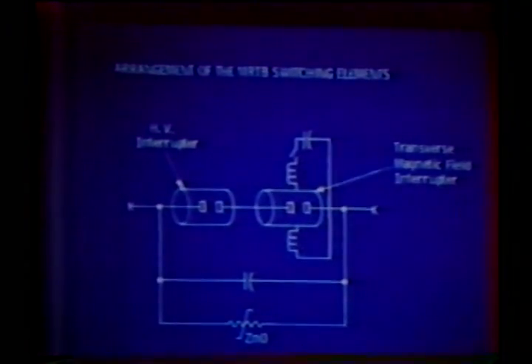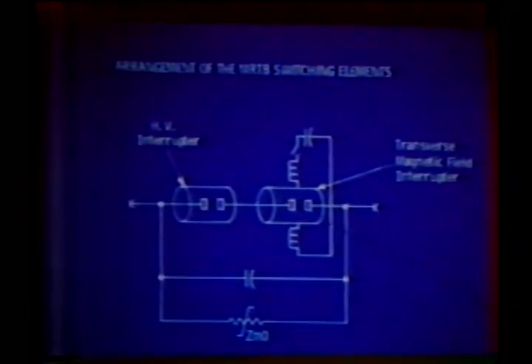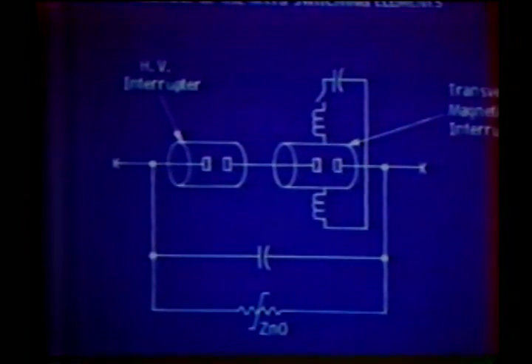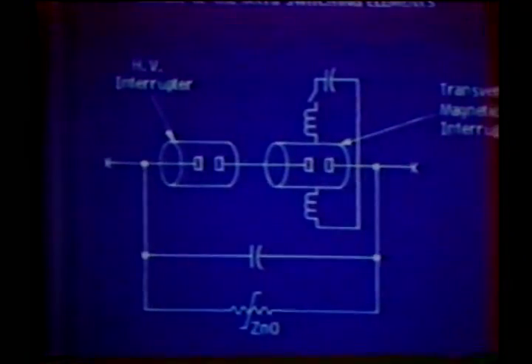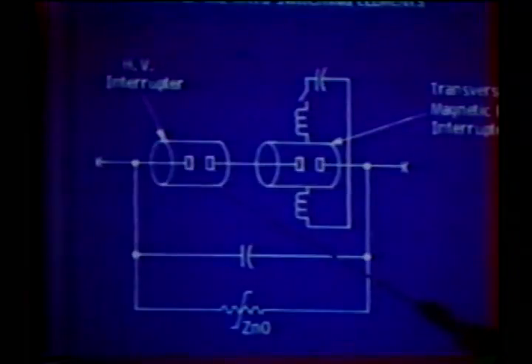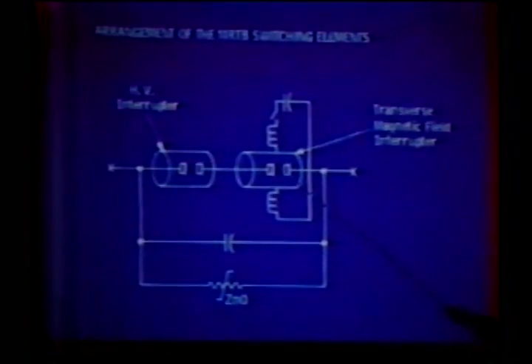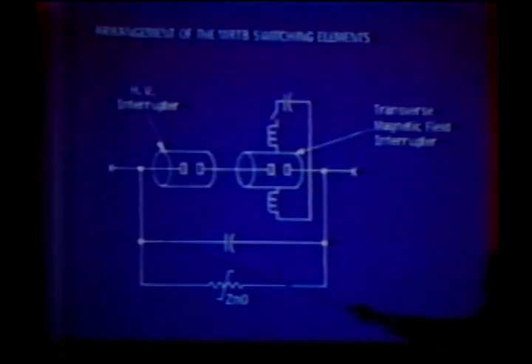For the metallic return transfer breaker, it was necessary to commutate current into a zinc oxide varistor and develop 80 kV across this varistor to drive current from a ground return into a metallic return. The way it was done was to put a high-voltage vacuum interrupter in series with a second interrupter to which a transverse field was rapidly applied. This changed the arc voltage from 20 volts to about 3,000 volts within a few microseconds, and in the presence of a parallel capacitor caused the current to divert into the capacitor. Both gaps then recover and the current is forced to continue flowing into the capacitor and ultimately into the varistor. A photograph of that device is shown here — this is the high-voltage interrupter, this is the commutation mechanism, and here are a couple of magnetic field coils where you apply a transverse field to force arc instability.